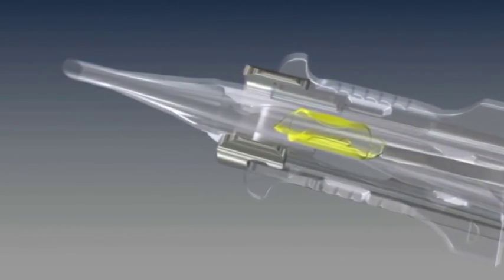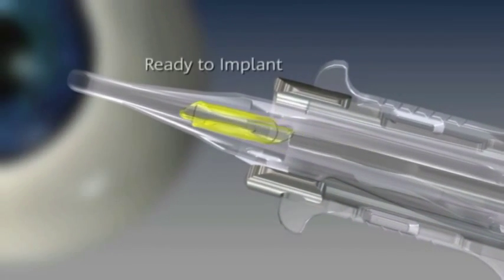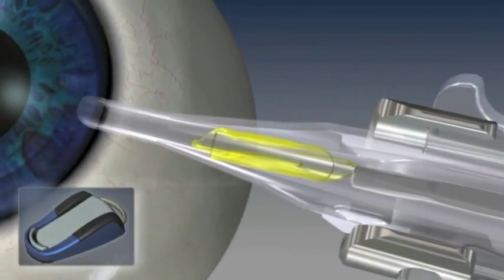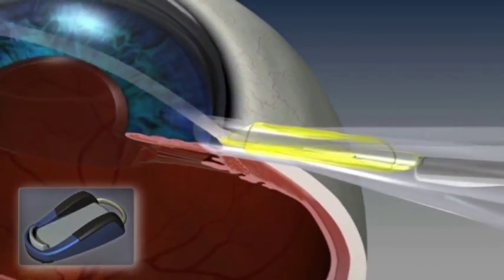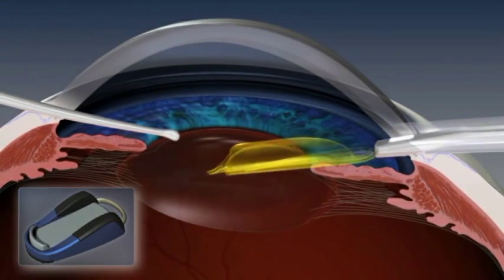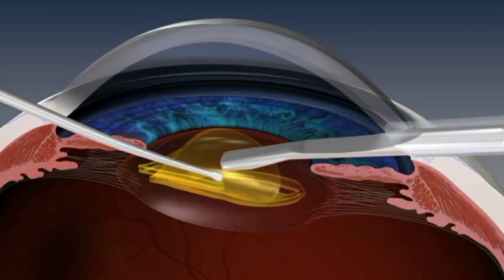Only now, with AutoSert, the software will automatically advance the IOL to the ready-to-implant position. The IOL insertion is completed under surgeon foot switch control, which can be customised to respond to patient needs and surgeon preferences for IOL material and incision size.